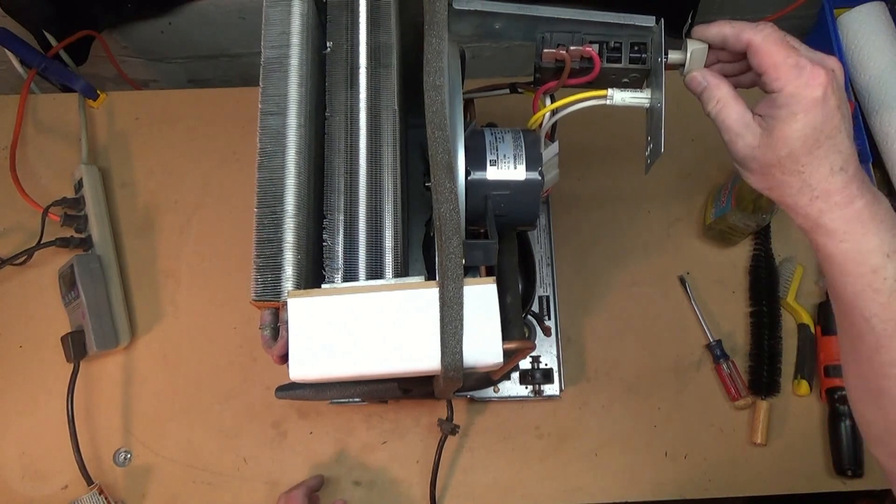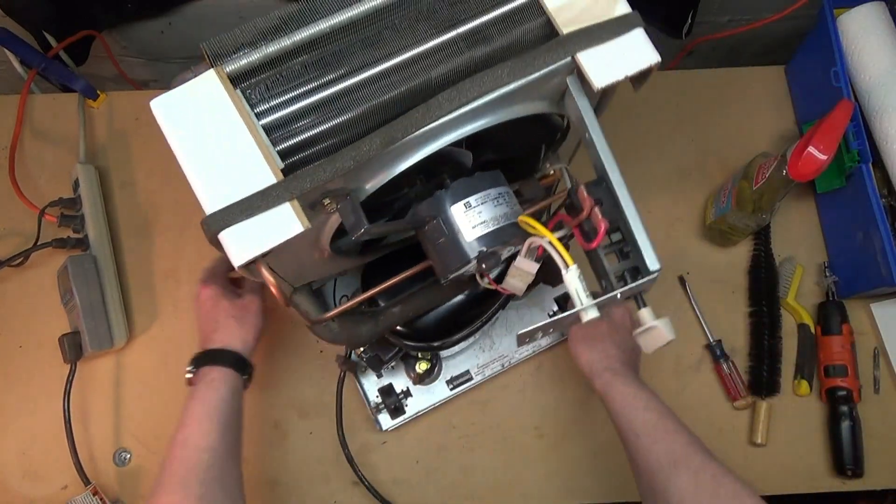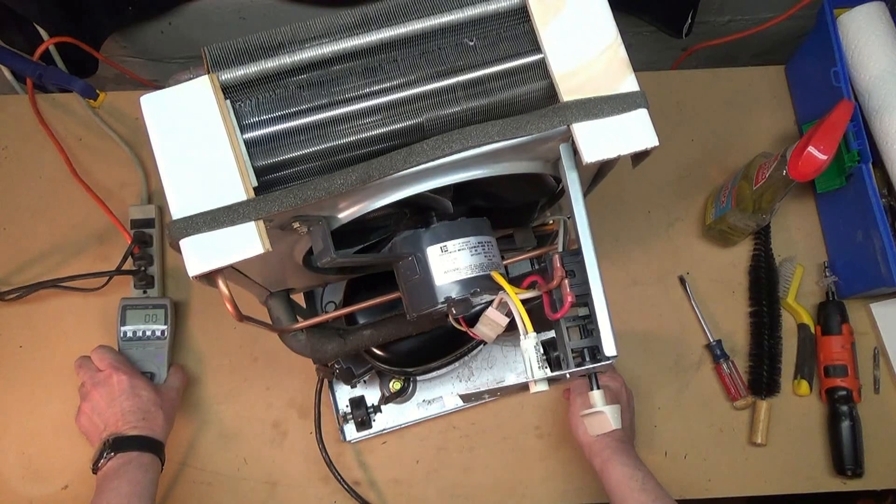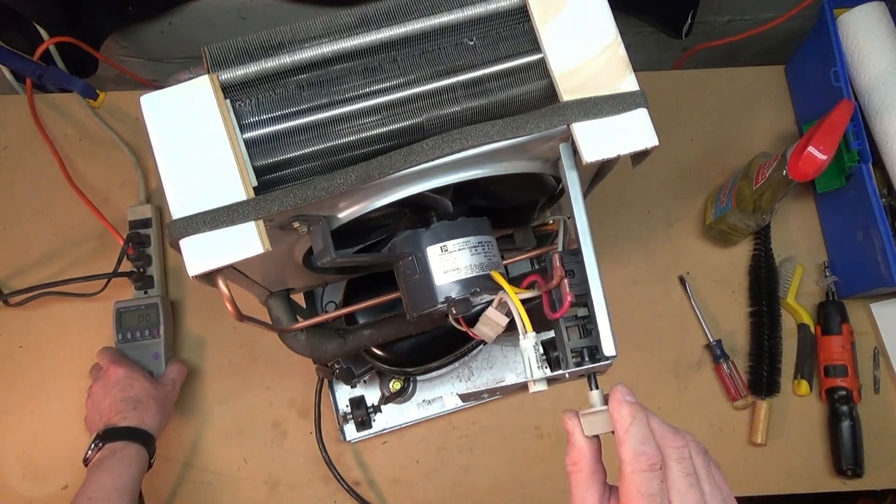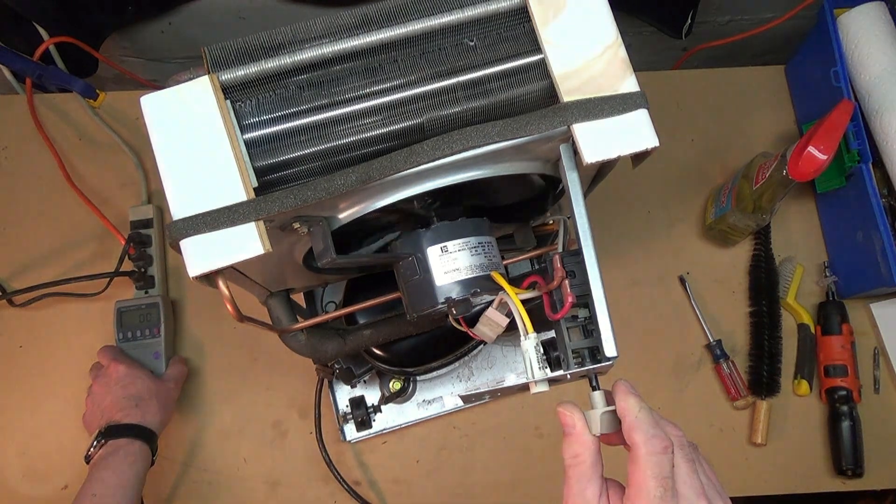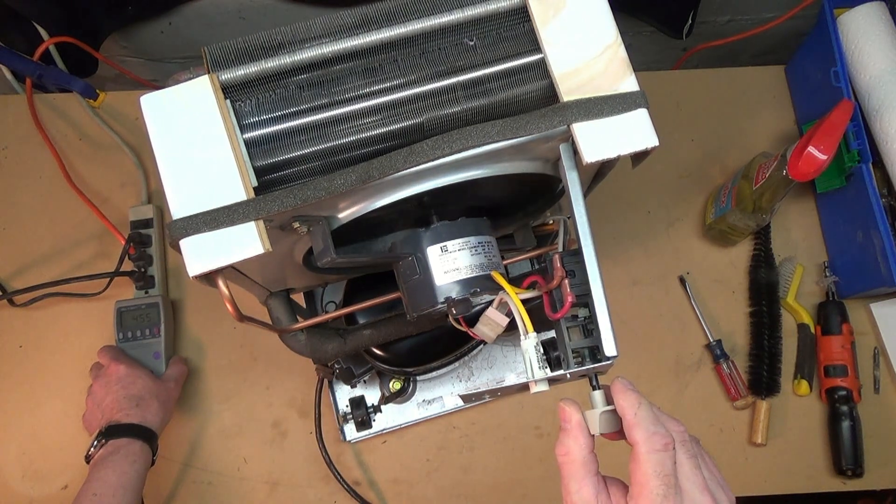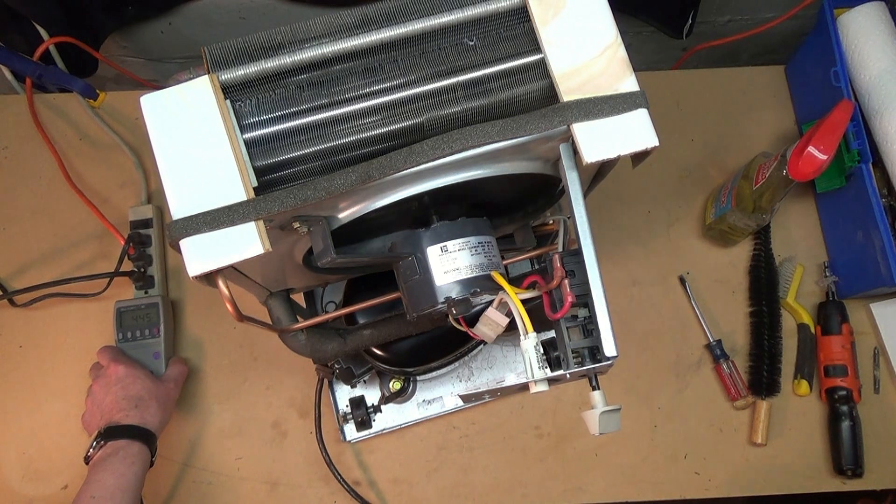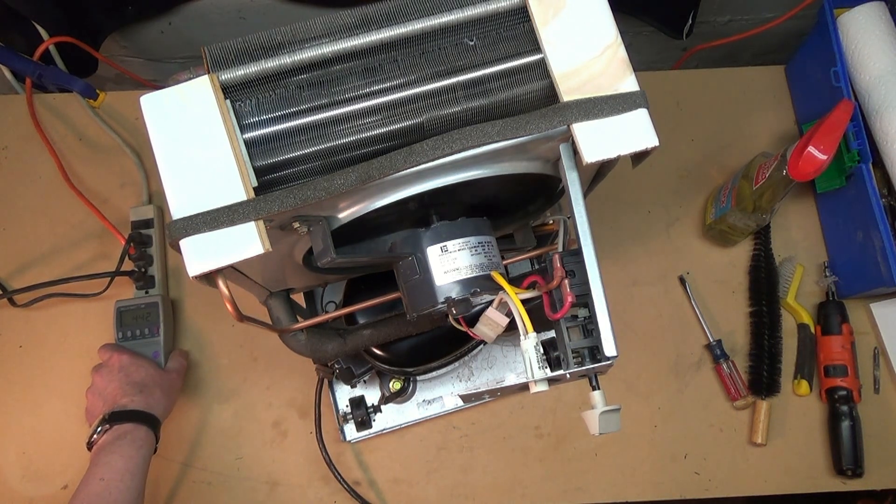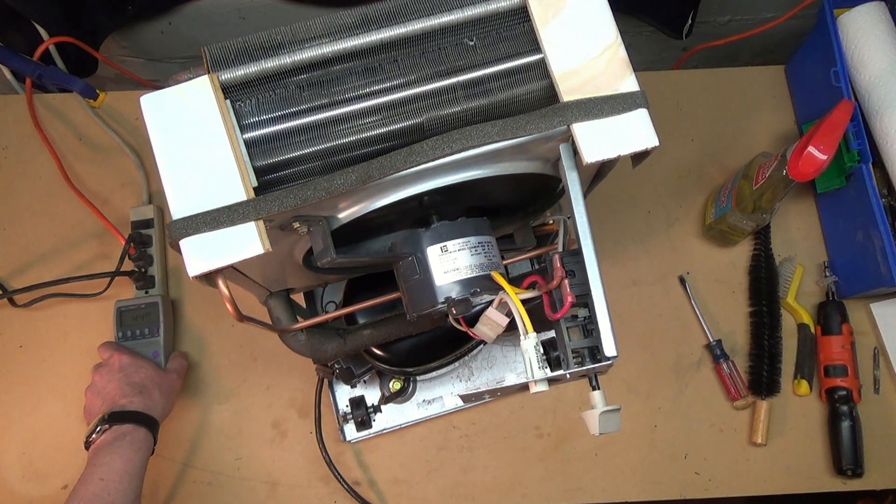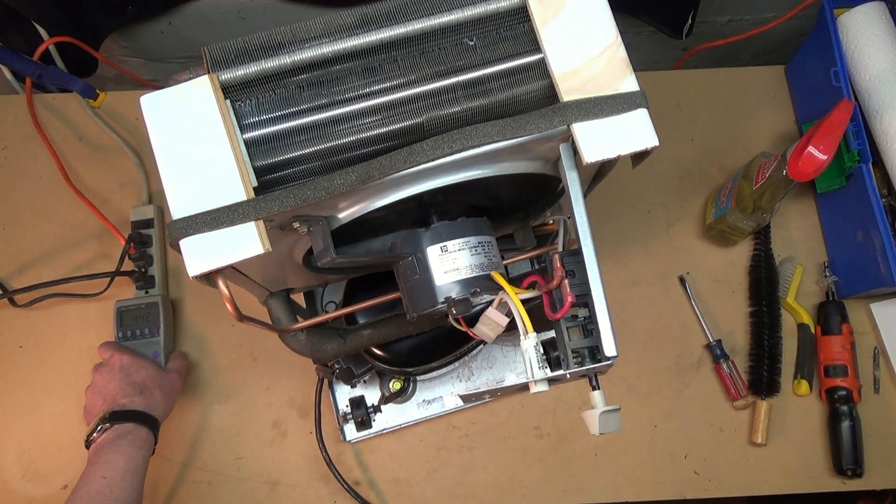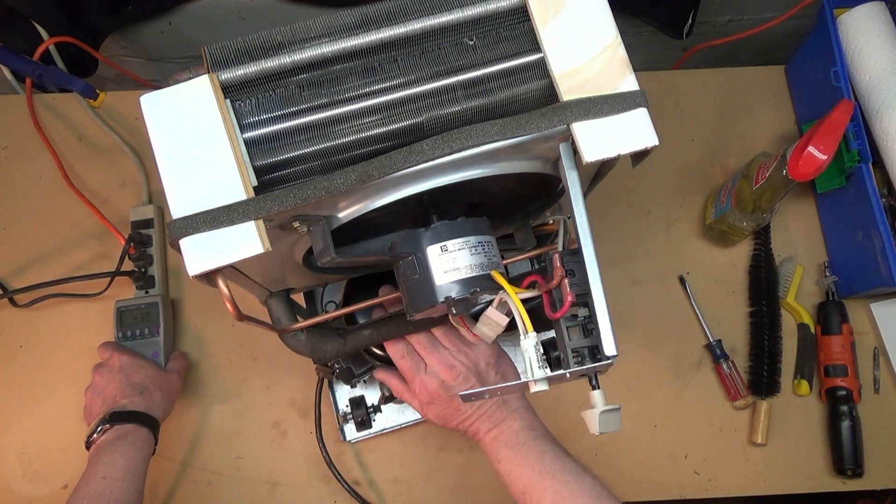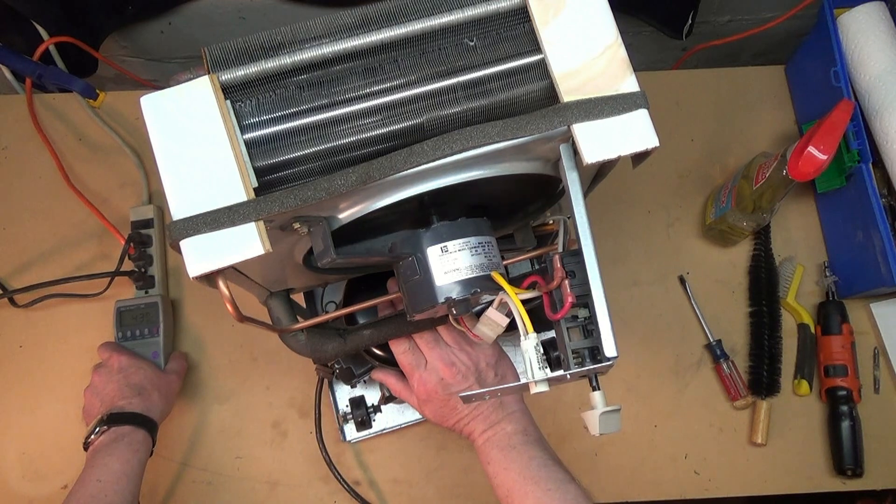So the unit is in the off position, and right now it is using no electricity. As we turn this, it should come on. Both the fan and the compressor came on. That's fine. They come on together all the time. It's only drawing together. They draw about 400 watts. That's about a third of a hair dryer.